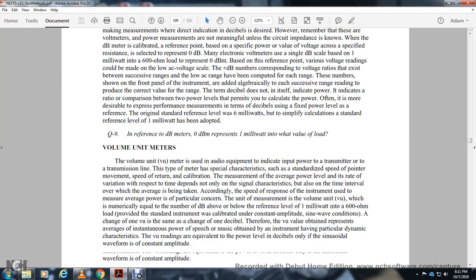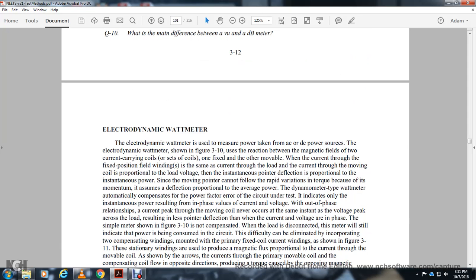The electrodynamic watt meter measures power from AC and DC power sources. It operates on the reaction between the magnetic field of a current-carrying fixed coil and a movable current-carrying coil. The current through the fixed position field windings is the same as the load current, and the current through the moving coil is proportional to the load voltage. The instantaneous deflection is proportional to instantaneous power, and since the moving pointer cannot follow rapid variation, the deflection represents average power. The dynamometer type watt meter automatically compensates for power factor.